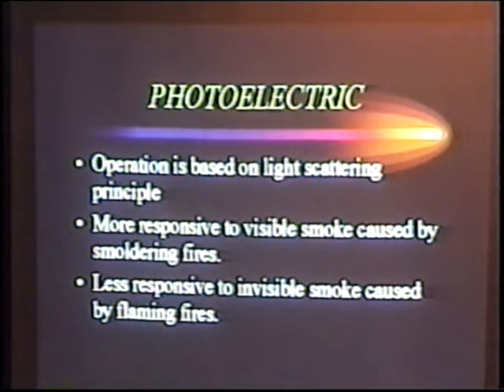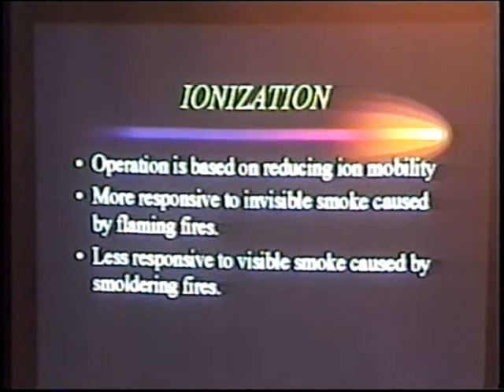The most important thing I want to talk about is when to use a photoelectric smoke detector. Photoelectrics tend to be more responsive to visible smoke caused by smoldering fire. The smoldering fire grows without flame and produces lots of particles. The particles go in the detector, more reflection. But photoelectrics tend to be a little less responsive to invisible smoke caused by flaming fires. That's where we're going to want to use an ionization detector, which we're talking about right now.